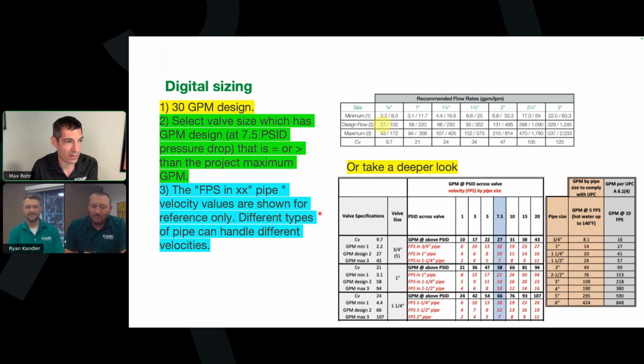Every piping material that carries a listing, appropriate that a jurisdiction will allow it to be used in a plumbing system, will work in these scenarios. You just have to figure out what their velocity speed limit is, essentially, like Matt's saying. So let's take a deeper look at this 30 GPM design scenario. We use the easy chart up here to find, okay, 3/4 inch valve looks like it's about right, but what does that mean for velocities?